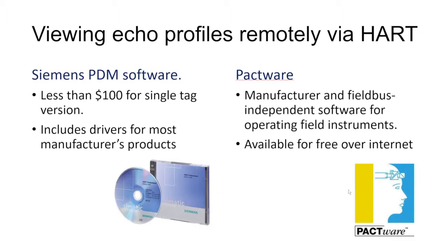Pactware is a product that's manufacturer and field bus independent. From that you will download drivers from the Siemens website for all the products you need to communicate to. The nice thing about HART is if it's a sensor in a remote location on top of a silo or in terrible weather, you can communicate to it remotely indoors and actually get a better resolution echo profile than you can on the integral display.